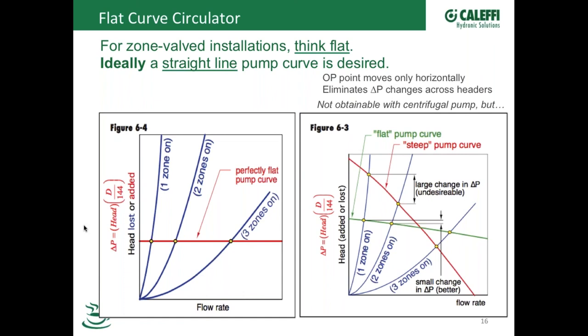So if you're going to use a circulator and you're going to have multiple zone valves on it, really what you'd like to do is pick a circulator that has a flat pump curve. Now, a perfectly flat curve, like we're showing in Nick's example, just isn't possible. You can't make a centrifugal pump with a flat curve like that. But some of the pumps have a fairly flat curve.